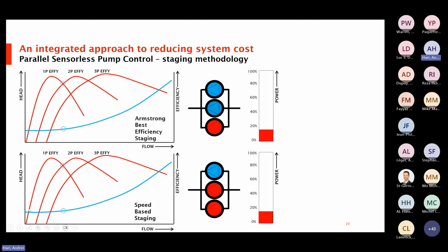And on a traditional system, that DP sensor will send a signal, and we will continue to pump until we reach basically 90% of that pump's capacity. Whereas with efficiency-based staging, the efficiency of the pump is incorporated into the staging logic. We look at when that pump crests its peak efficiency and starts dropping down, and we stage the second pump on, as opposed to letting that pump run to its 90% point. Typically, that means you may be staging your pumps anywhere around 50 to 65% of their design load, as opposed to running it to 90%.